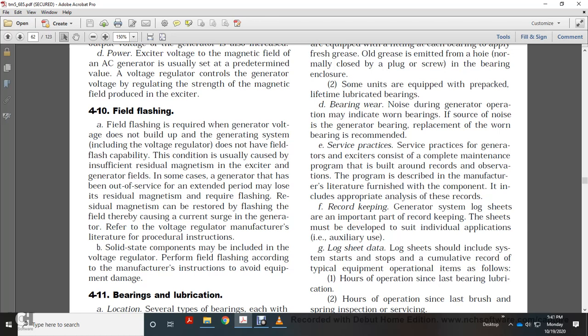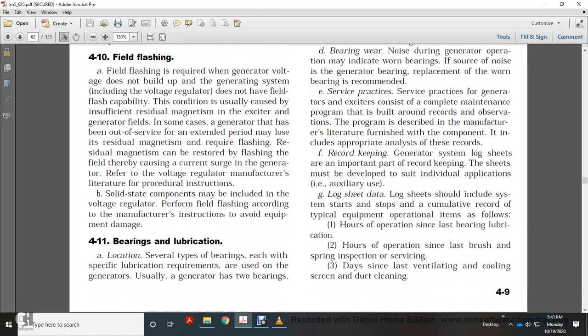Residual magnetism can be restored by flashing the field, thereby causing a current surge in the generator. Refer to the voltage regulator manufacturer's literature for procedural instructions. Solid state components may include a voltage regulator that performs field flashing according to the manufacturer's instructions, to avoid equipment damage.